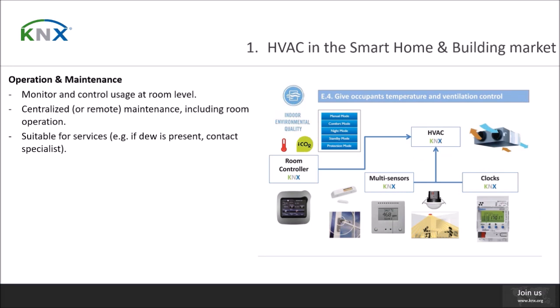From the operation and maintenance point of view, there is an increased demand to offer occupants the control, room level again, but also to be able to override the user's control if needed. Another key factor from KNX is that the same sensor can play an important role in the energy saving, but also in the operation and maintenance. This translates into savings from the construction point of view. A good example of this duality is dew sensors. They are part of the maintenance, avoiding issues, but they can also become part of services. For example, if dew is present for a number of days, the specialist can be contacted to go and have a look.